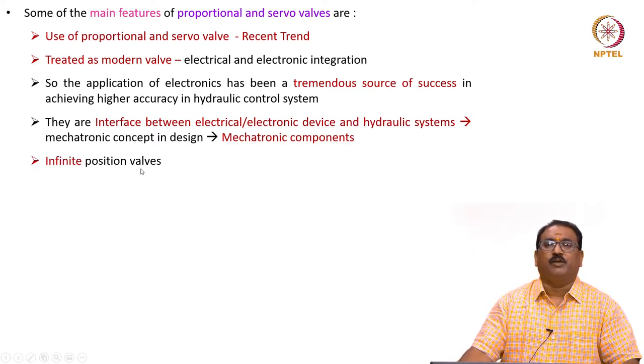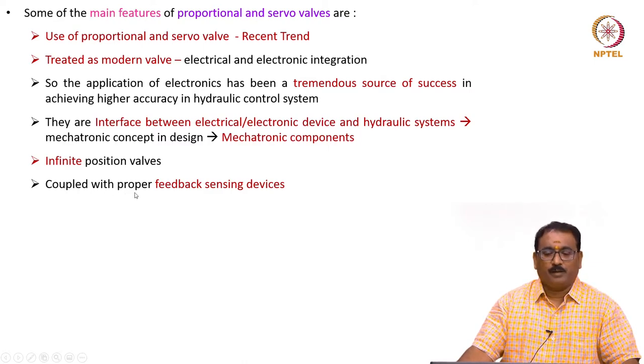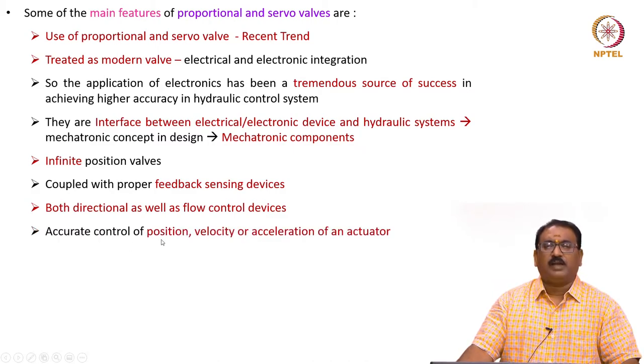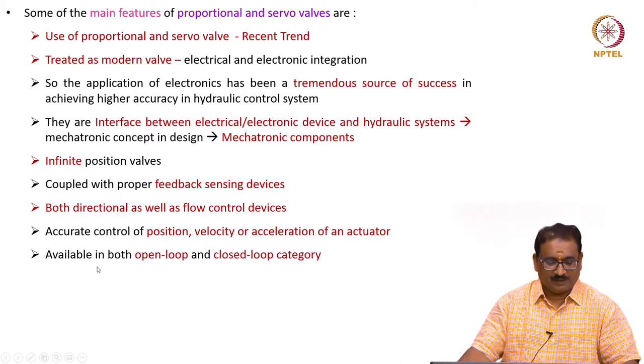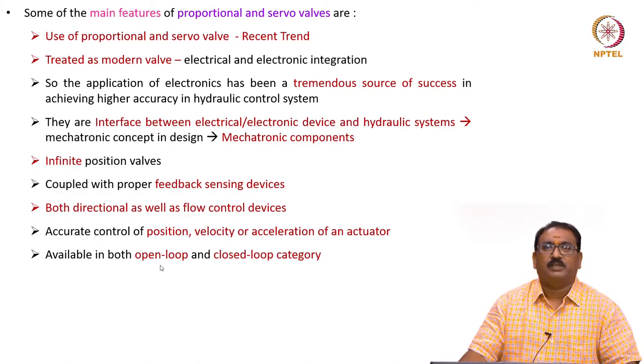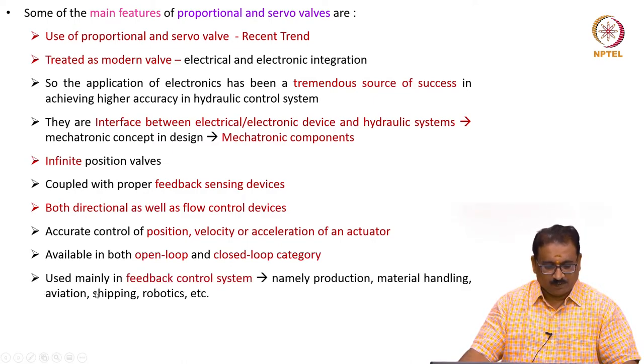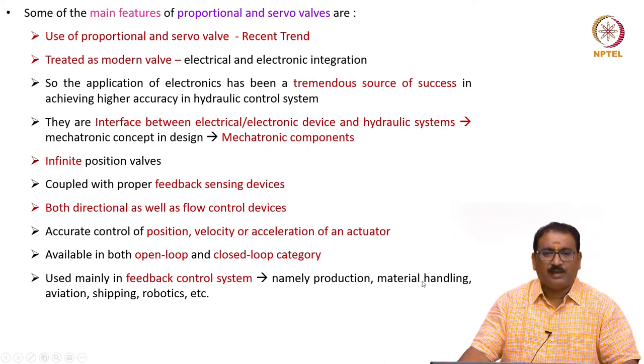Infinite-position valves, they are coupled with proper feedback sensing devices. They are available as both directional and flow control valves. Accurate control of position, velocity, or acceleration of an actuator is ensured. They are available in both open-loop and closed-loop categories. Please remember: servo valves always work on a closed-loop basis, while proportional valves are open-loop but are now being extended to closed-loop as well. They are used mainly in feedback control systems — in production, material handling, aviation, shipping, robotics, and many other places.